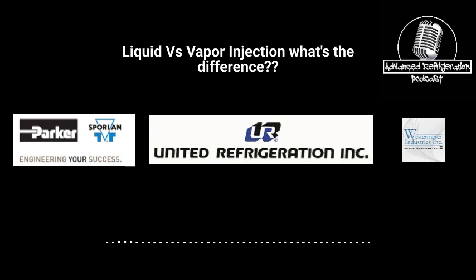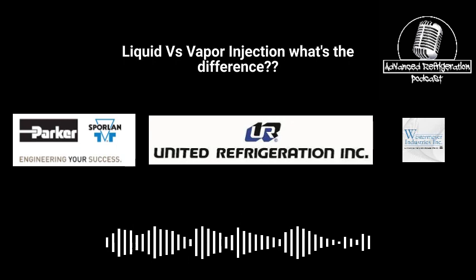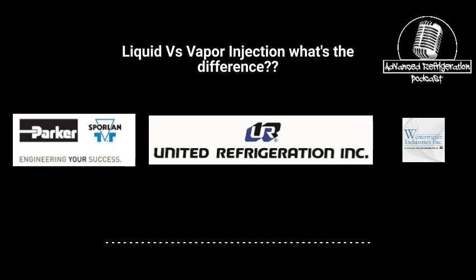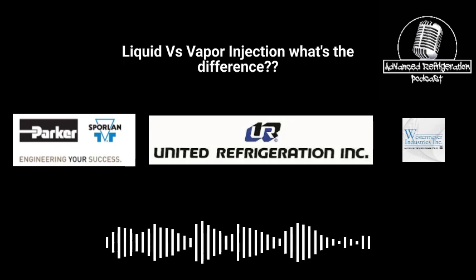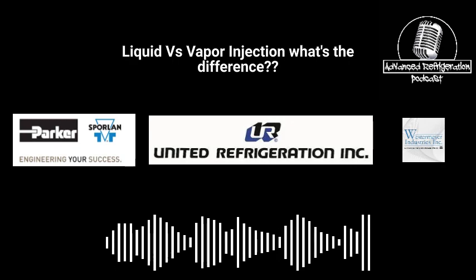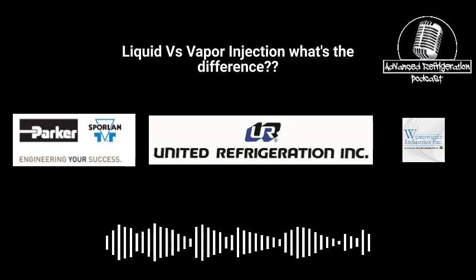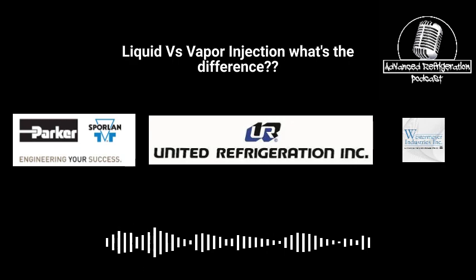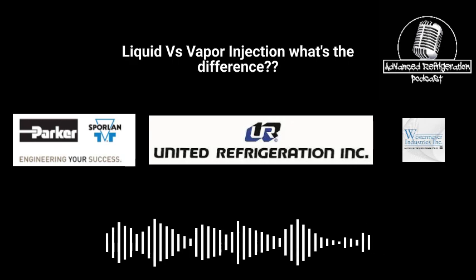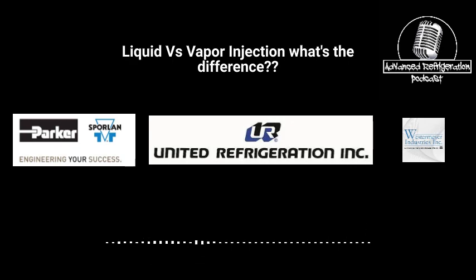Someone called me up. They're like, yeah, there's a liquid injection line. I was like, no, it's vapor injection. He was like, well, how do you know? I was like, read me off the model number of the compressor. And sure enough. I asked, what are your numbers? He had like 30 degrees of superheat on the suction, but his discharge line temperature was 70 degrees on a running compressor. So no bueno.